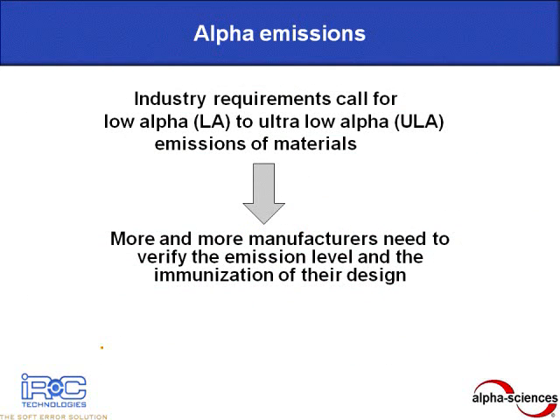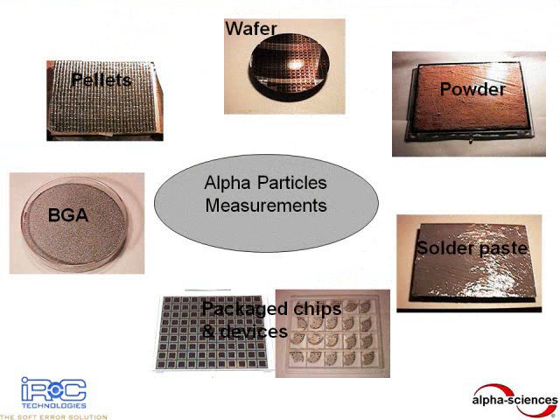Our team has the ability to measure and report the alpha emission of materials based on over 25 years of providing alpha detection equipment and services. By constantly updating and improving the design and materials of the equipment, we can measure nearly any type of sample, from complete IC devices down to individual materials in the form of sheets, pellets, silicon wafers, pastes, and powders. If it can be placed in the counting chamber, it can be measured, and no sample preparation is required other than placing the sample onto the sample tray and into the counting chamber.